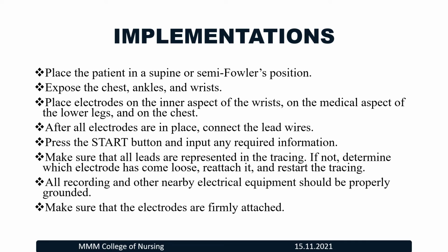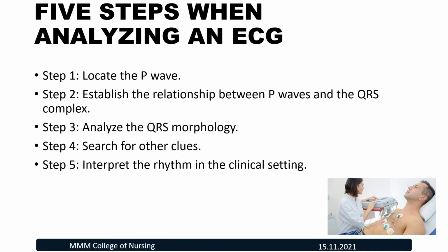Press the start button and input any required information. Make sure that all leads are represented in the tracing. If not, determine which electrode has come loose, reattach it and restart the tracing. The recording and other nearby electrical equipment should be properly grounded. Make sure that the electrodes are firmly attached.